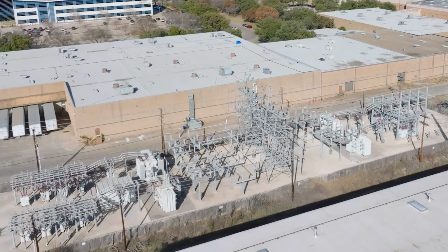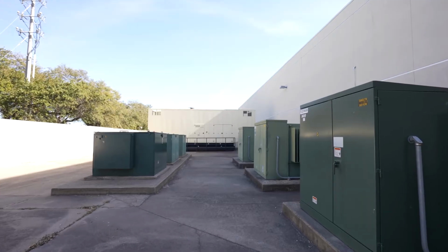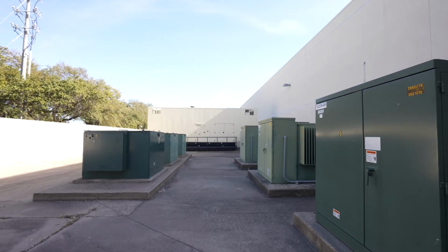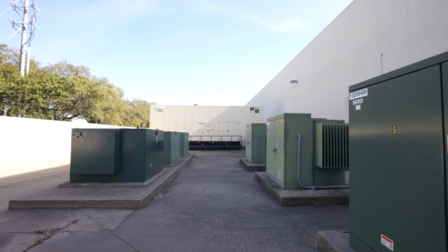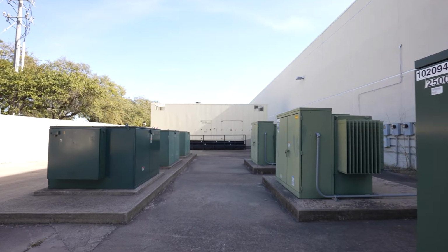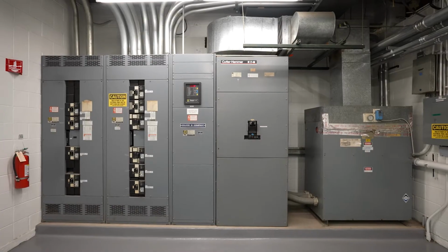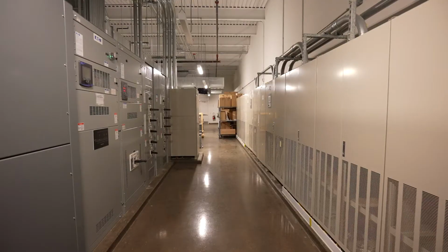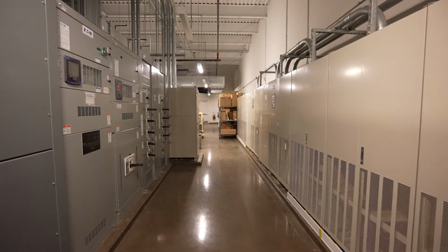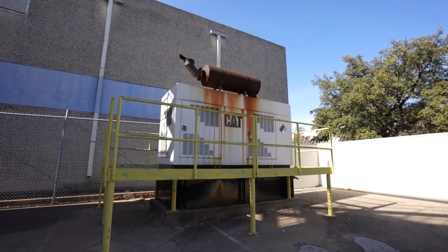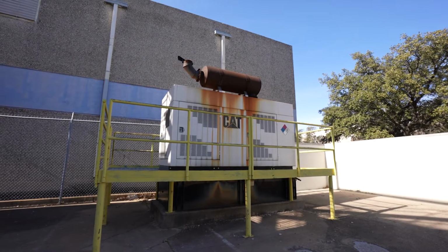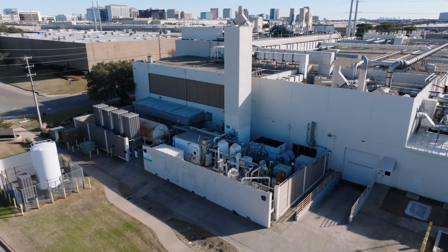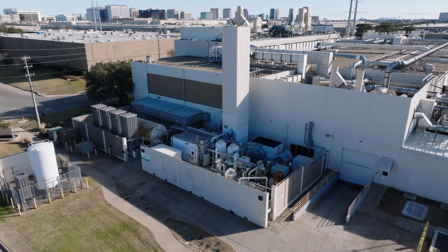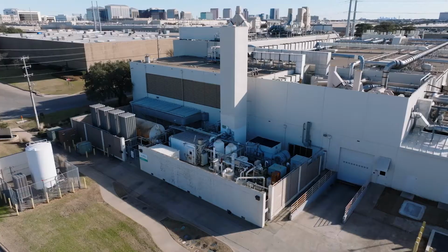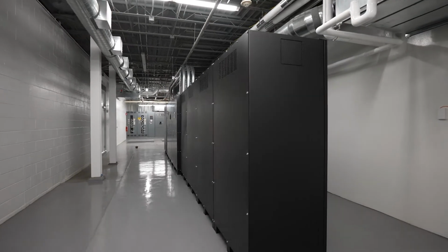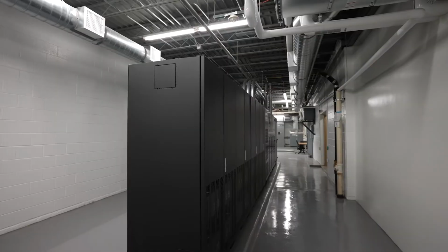Overall, the facility features ample power with 2 4,000-amp, 277/480-volt, 3-phase redundant electrical services, providing from 2 2,500 kVA transformers and terminate in a 4,000-amp static transfer switch, extending to a main switchboard for distribution throughout the area. Multiple diesel generators support Building A, 200 kilowatt, 500 kilowatt, and a 750 kilowatt diesel generator provide backup power throughout Building A. Additionally, there are 2 new 1 megawatt UPS units installed in Building A.